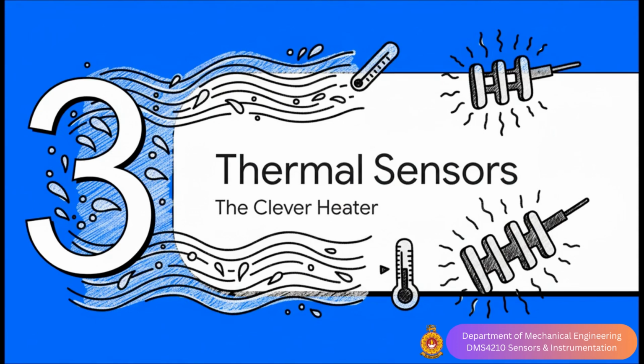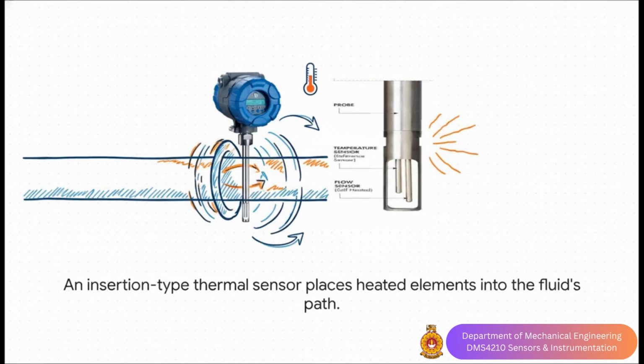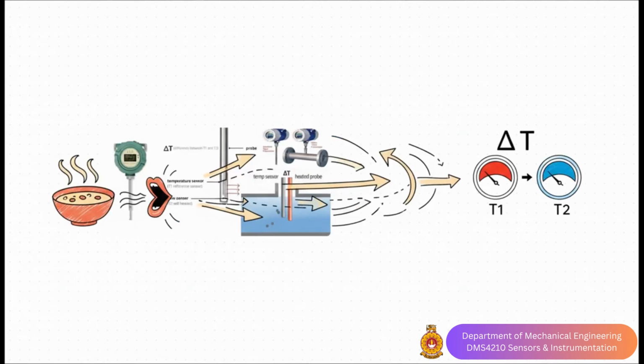Okay, so what if your application just can't have any moving parts getting in the way? Well, this is where things get really, really clever. Our next tool uses a completely different and brilliant principle: heat. Instead of being pushed by the fluid, this sensor measures how much the fluid cools it down. What you're looking at here is a thermal mass flow sensor. See that long probe? That gets inserted right into the pipe, directly into the flow. And at the very tip of that probe is where all the magic happens. It actually has two tiny sensors, one that measures the fluid's natural temperature, and another one that's heated to a specific temperature above that.